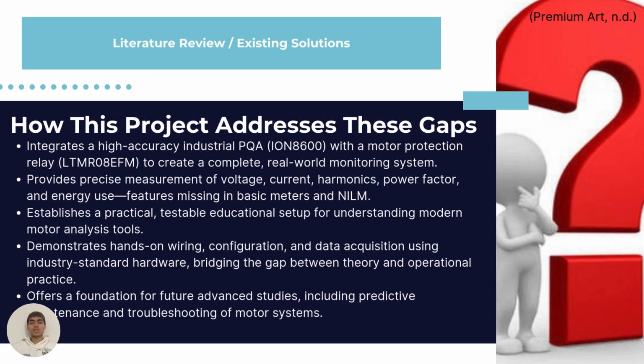So how does this project address these gaps? It integrates a high accuracy industrial power quality analyzer, the ION 8600, and a motor protection relay to create a complete real world monitoring system. It provides precise measurement of voltage, current, harmonics, power factor, and energy use, features missing in basic meters and NILM. It establishes a practical, testable educational setup for understanding modern motor analysis tools. It demonstrates hands-on wiring configuration and data acquisition using industry standard hardware, bridging the gap between theory and operational practice.